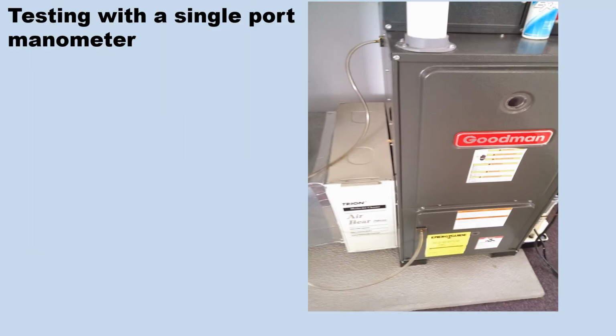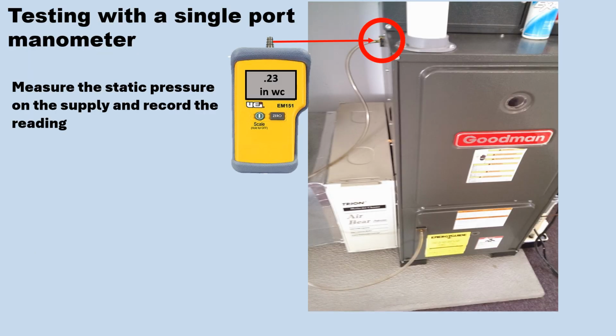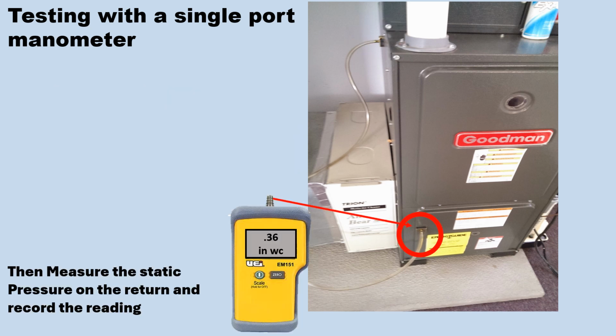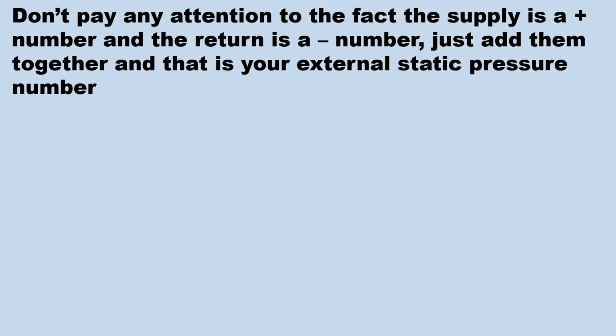Testing with a single port manometer: measure the static pressure on the supply and record the reading. Then measure the static pressure on the return side and record the reading. Just remember, it doesn't matter which one you measure first. You just have to measure both. Don't pay any attention to the fact that the supply is a positive number and the return is a negative number. Just discard the plus and minus and add them together, and that is your total external static pressure number.